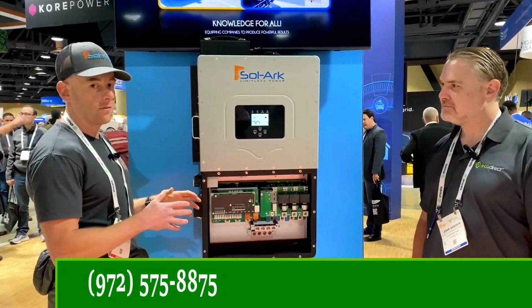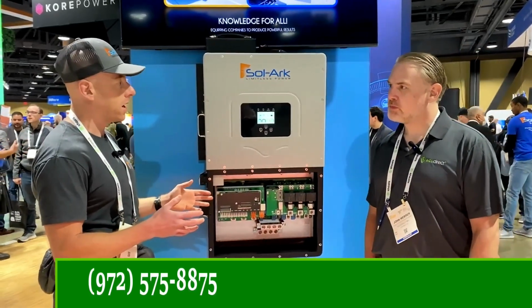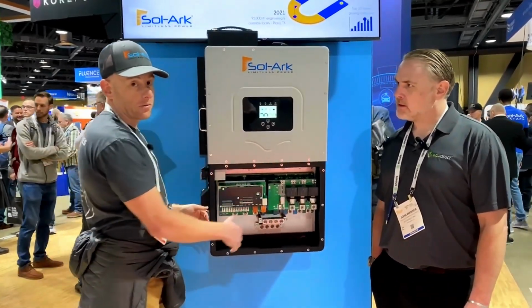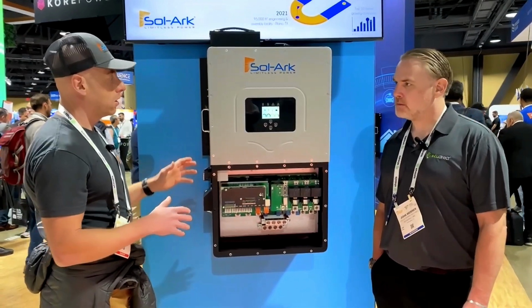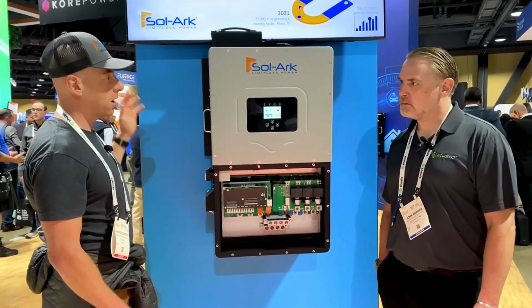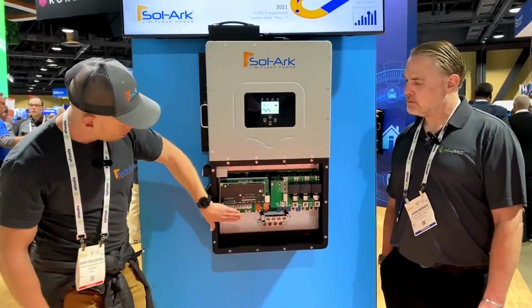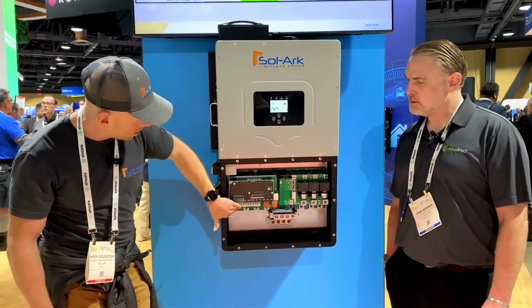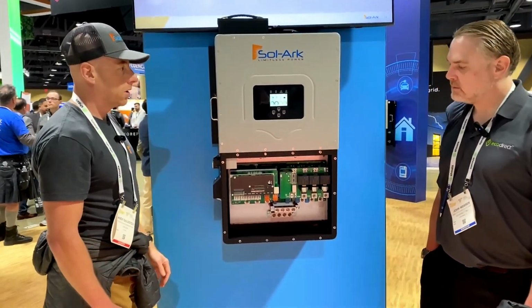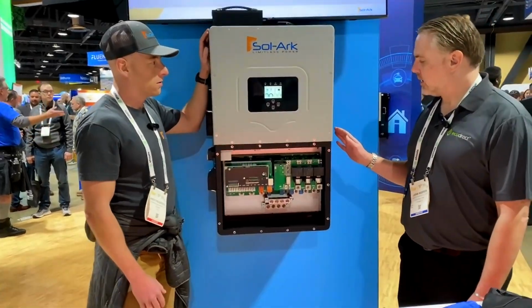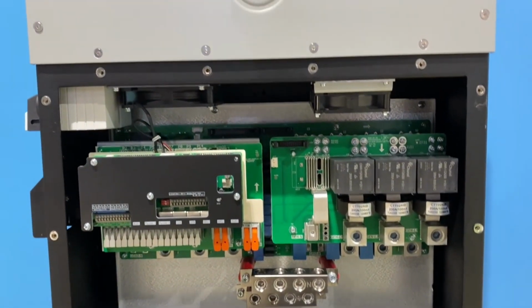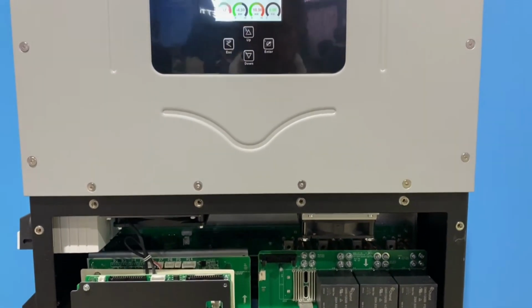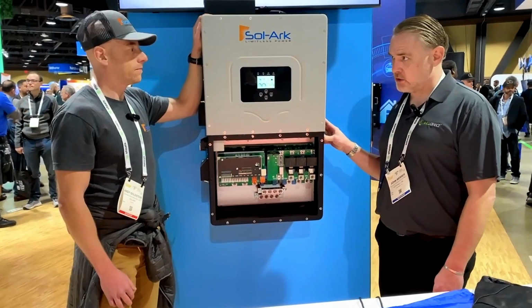But suffice to say, if you have an existing solar array and you want to AC couple, you can do that. If you have a brand new install, you just take up to 39 kilowatts of PV, go right into our MPPTs here, and you can do it that way as well. So I hope I answered your question. For a commercial customer that's already had PV on the roof for 5 or 6 years, this is a very easy way for them to add storage to it.